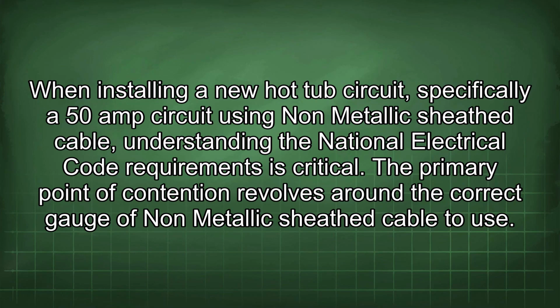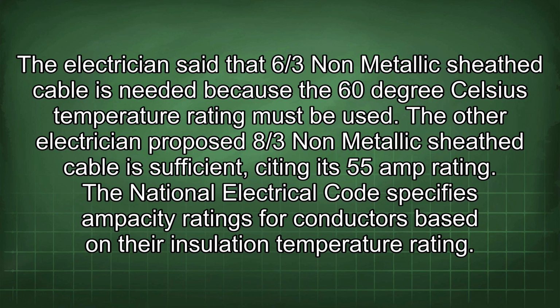When installing a new hot tub circuit, specifically a 50-amp circuit using non-metallic sheath cable, understanding the National Electrical Code requirements is critical. The primary point of contention revolves around the correct gauge of non-metallic sheath cable to use. One electrician said that 6/3 non-metallic sheath cable is needed because the 60°C temperature rating must be used. The other electrician proposed 8/3 non-metallic sheath cable is sufficient, citing its 55-amp rating.